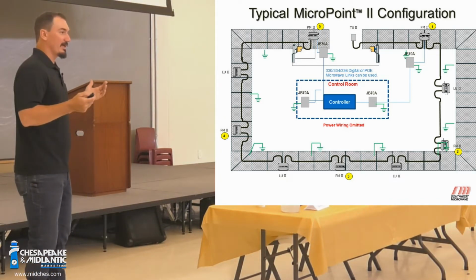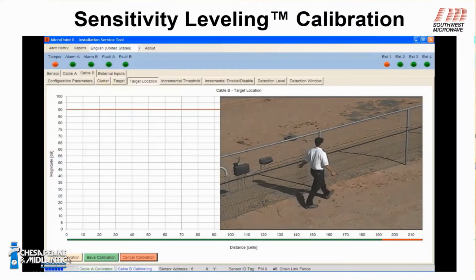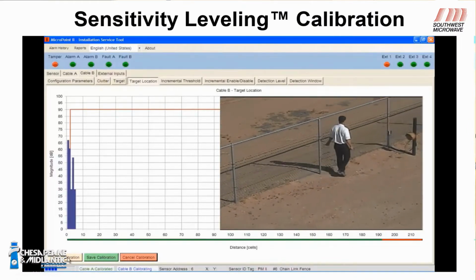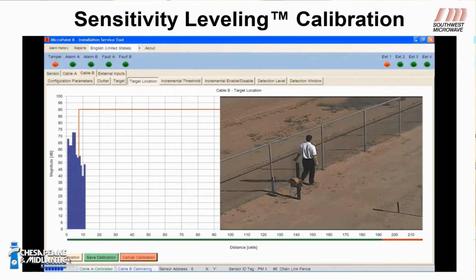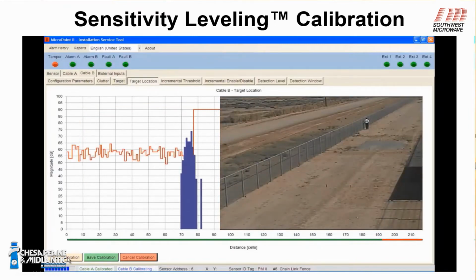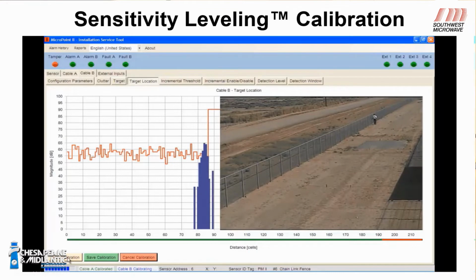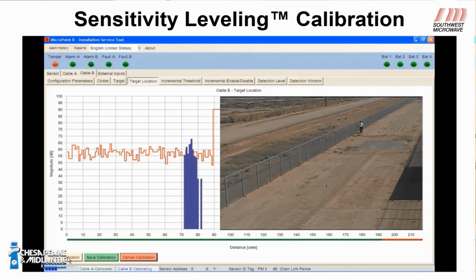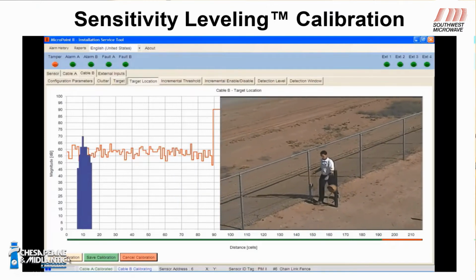So you might be wondering what a calibration looks like. We take a metal object, we drag along the fence. As we're dragging along the fence, what we're looking at here is the software tool the technicians use to install, calibrate, and tune and adjust the system. On the bottom, this is the distance from the processor in cells of 1.1 meter length. This is a magnitude of events, the strength of those events. This blue line is in real-time response to what's happening on the perimeter. And each of these little flat tick marks represents the strength of an event at that specific cell. Okay? So this is the system learning.